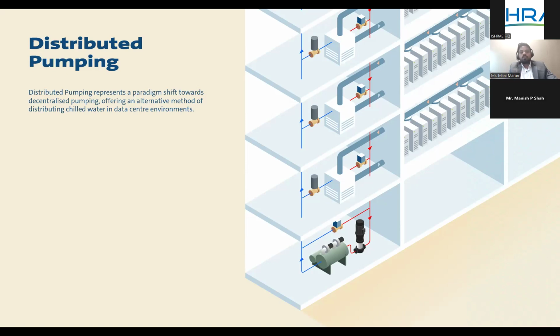Before jumping into this, let's see how we define efficiency in a data center. PUE is a benchmark for data center efficiency that we all know: power usage effectiveness. What is that? It's the ratio of the energy used by computing equipment and the support infrastructure, like cooling, which defines this metric. Now, coming back to the chilled water system and the pumping system, removing energy-consuming components while still maintaining efficiency and addressing the demand will drastically improve the PUE of the data center.